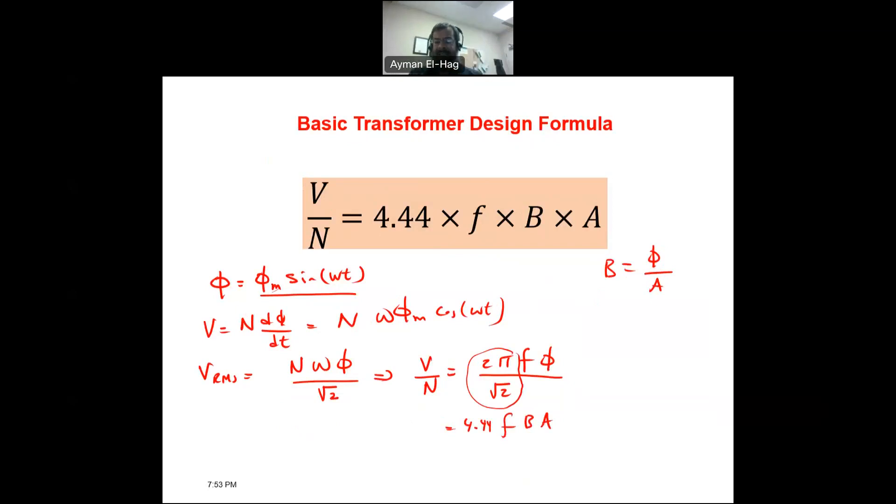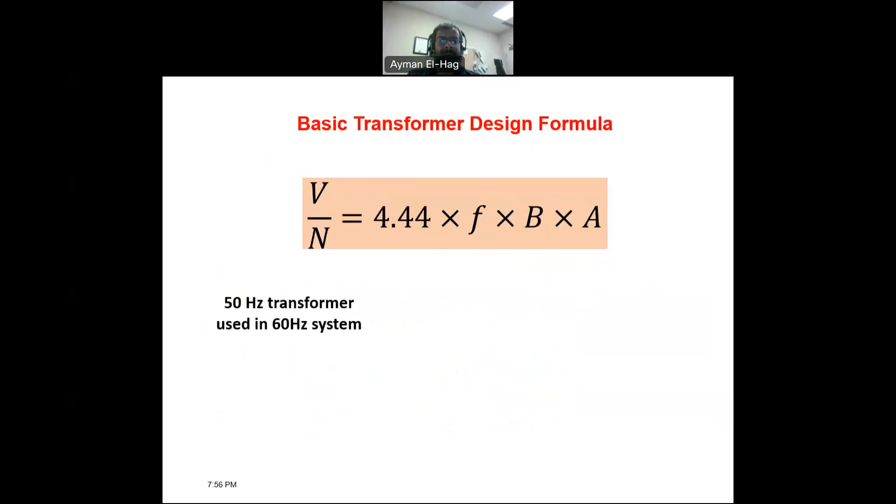Now, having this background, let's answer our question. And, let's start. If we have a 50 hertz transformer, and we use it in a 60 hertz system. So, now, when I design a transformer, A is now fixed. I cannot play with A. A is the cross-sectional area of your transformer core. Voltage per turn, I don't play with it. Number of turns is fixed. The voltage apply is fixed. So, this is fixed, and this is also fixed. Now, when I increase the frequency from 50 to 60 hertz, what will happen to the B? B, the flux density, will be reduced. Is this good or bad?